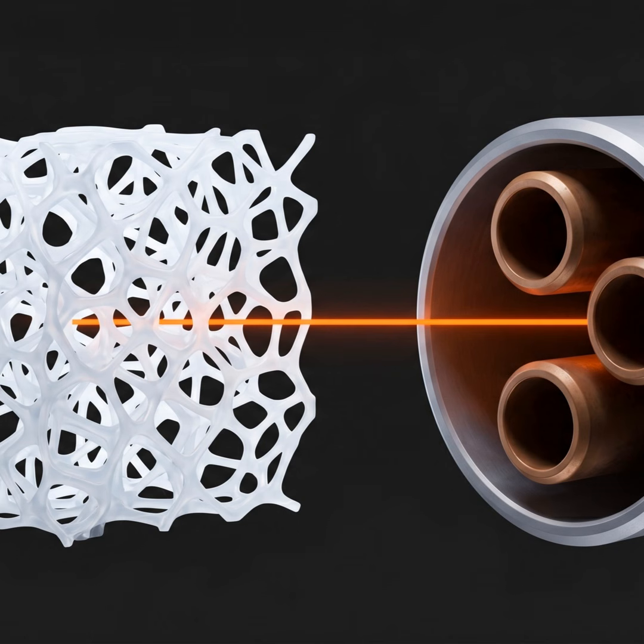Right. The moment that 250-degree gas hits one side of the plates, the frost on the lower water pipe instantly melts. The cold water absorbs the thermal energy from the gas and transforms into a warm, steady flow of 150-degree processed water. The superheat from the refrigerant is literally injected directly into the cold processed water. It's just elegant physics. It really is.